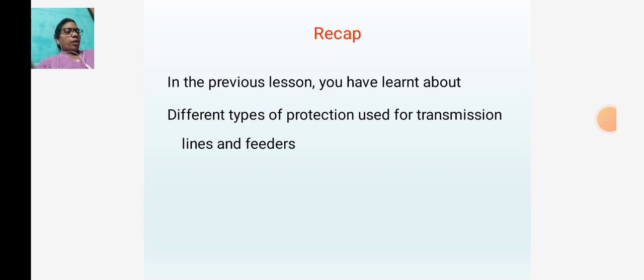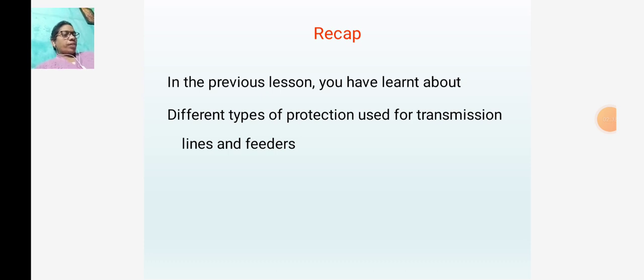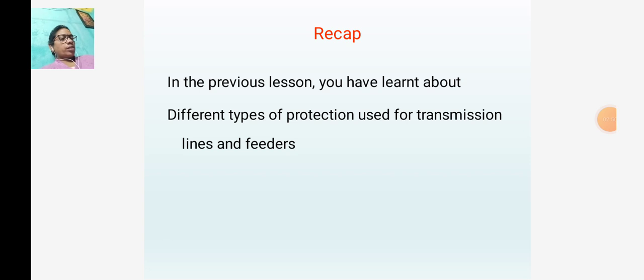In case of a fault on a bus bar, the fault current and power may be very large and cause serious damage to the system. Faults on bus bars may affect the continuity of a power system and cause discontinuation of power to a large portion of the system. The stability of the system is affected by faults in the bus zone. In large power systems, protection of bus bar sections is necessary so that faulty sections are isolated before the fault spreads over the whole system.